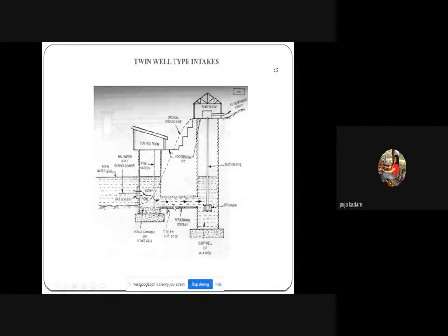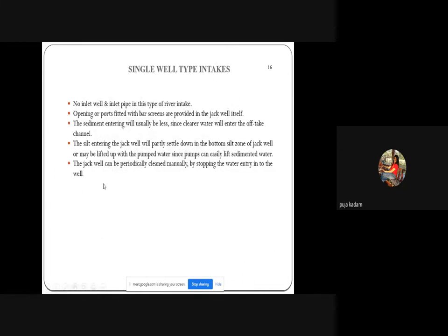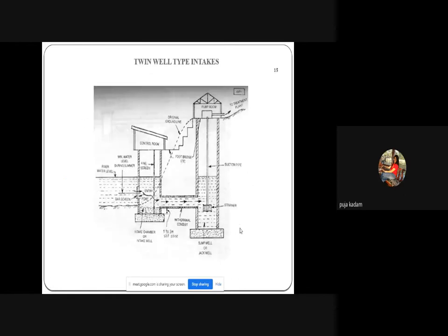The inlet well is usually circular in cross section and made of masonry or concrete. The inlet pipe connects the inlet well with the jack well, has a minimum diameter of 45 centimeters, is laid at a slope of 1 in 200, and flow velocity through it is less than 1.2 meters per second. Water entering the jack well is lifted by pumps and fed into the rising main. The jack well should be founded on hard strata with bearing capacity more than 450 kilonewtons per square meter.